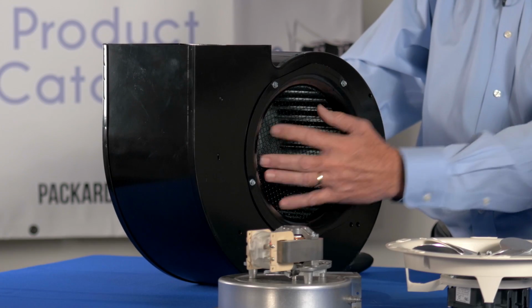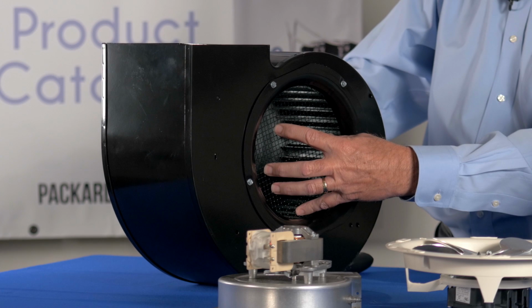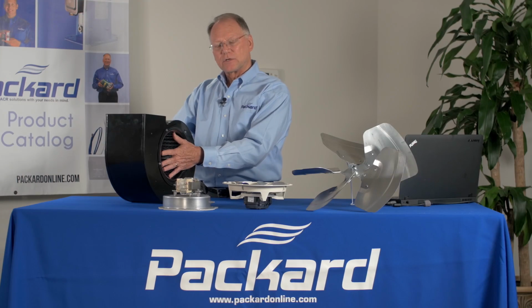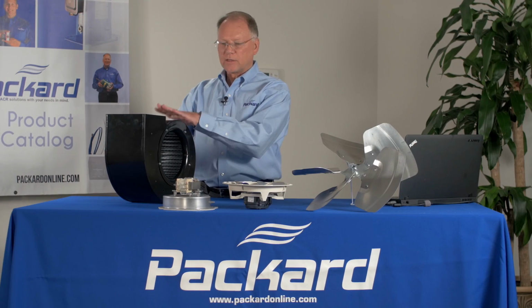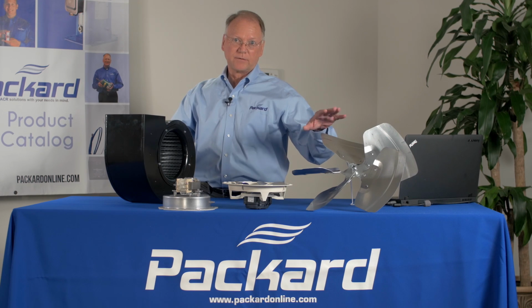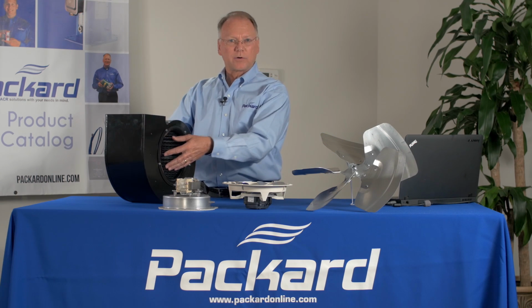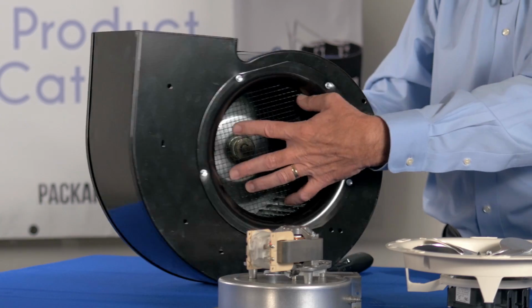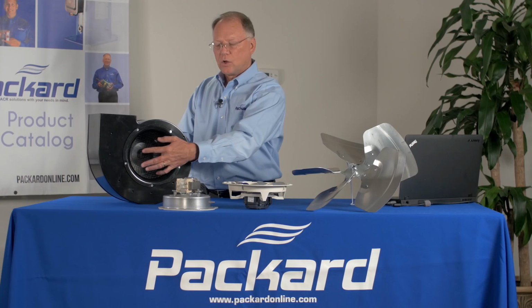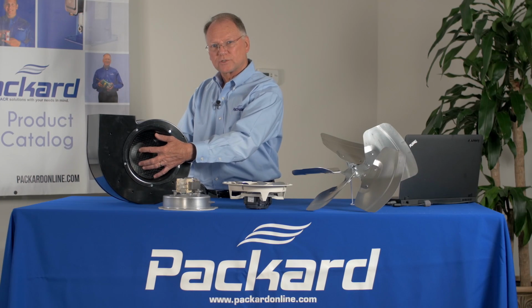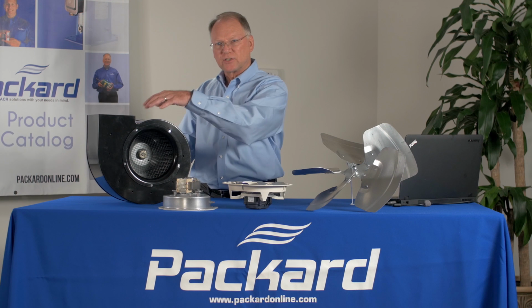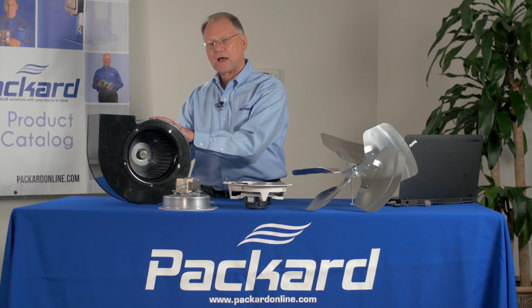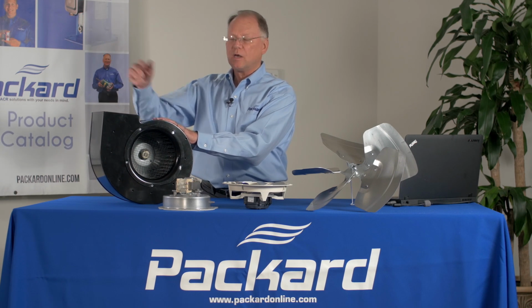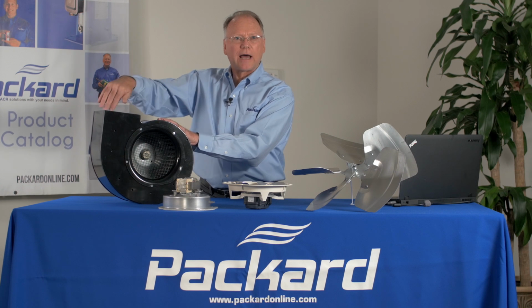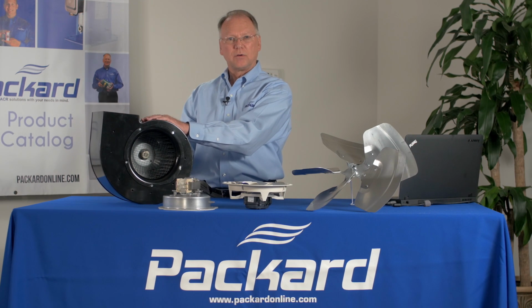So the blower brings the air in to the inlet, and a key difference between the blower and the axial fan is that on the blower, the air fills the inlet area through centrifugal force, is pressurized and thrown off into the housing and removed, but it comes in and goes out at a right angle.